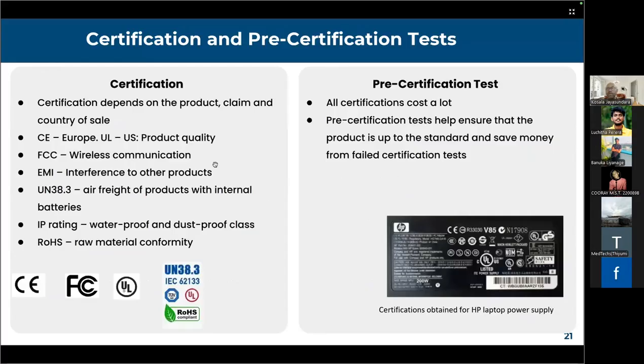And then you can go to certification, pre-certification, testing, everything. And that's a whole new ball game. As I mentioned, recently we got a quotation from a Taiwan supplier for certifications, IEC certifications, and all the other CE, EMC, EMI general certifications, and adherence to 60601, everything together for a TENS therapy device.